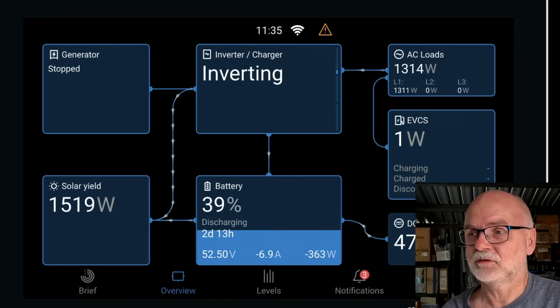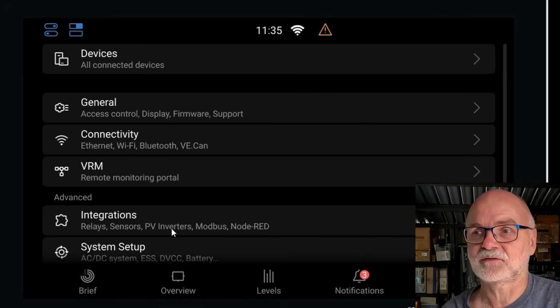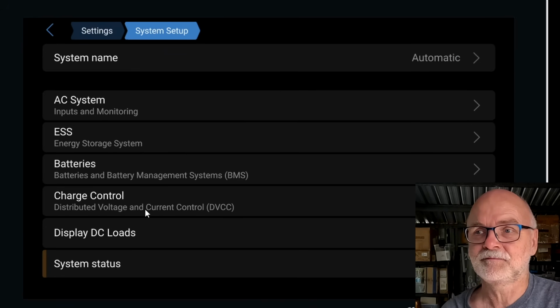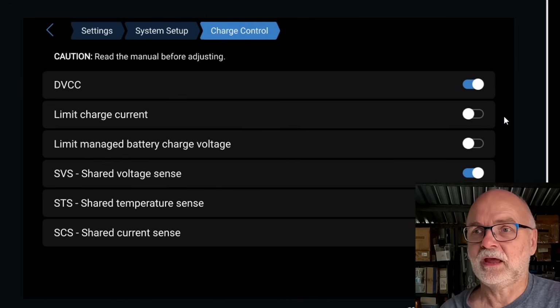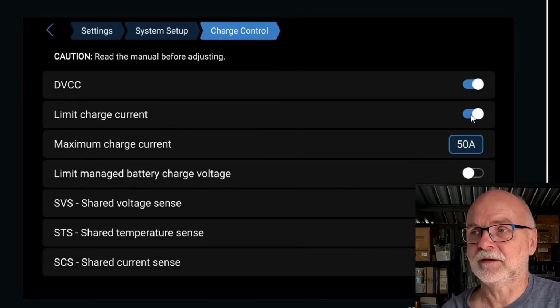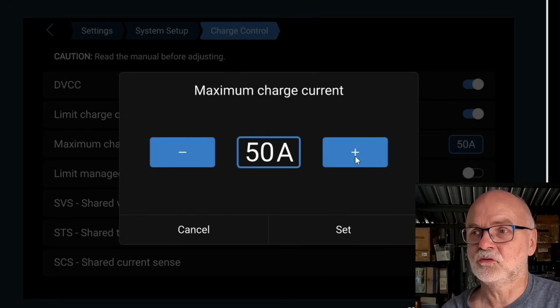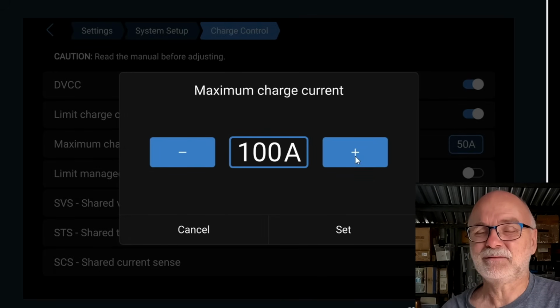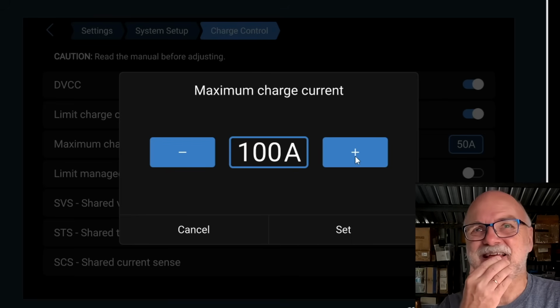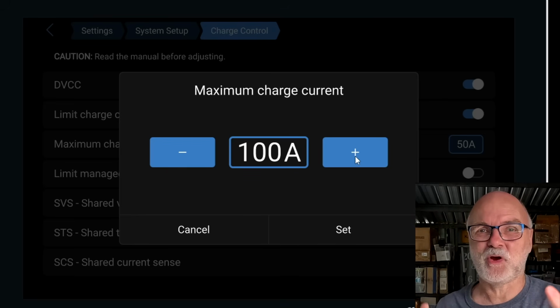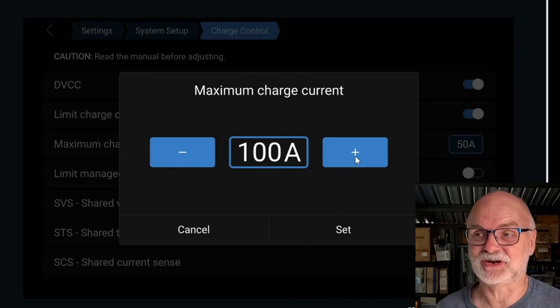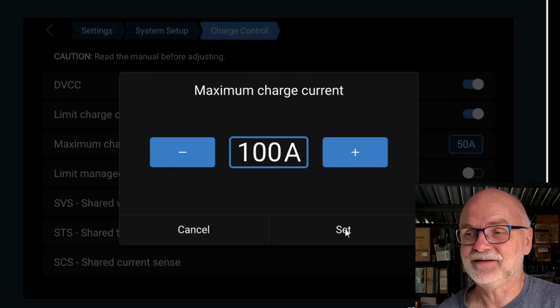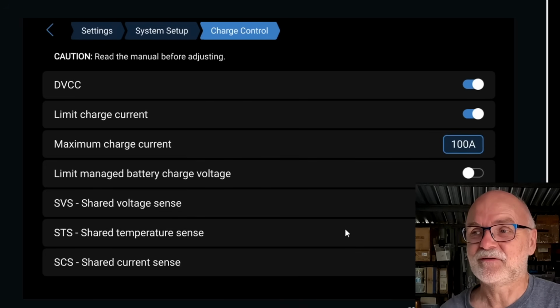So what we are going to do is going into the settings of the Victron system, going into the DVCC, charge control, and turn on limit charge current, yeah? And set this one to, I would say 100 amps. That would be 50 amps per battery. That is 0.5 C for each of the batteries roughly, if they are charging the same way. Yeah, 100 amps would be the limit for this installation now for these small batteries.